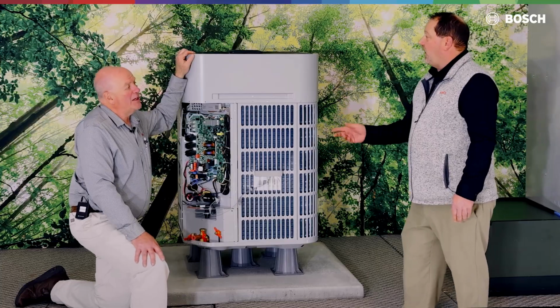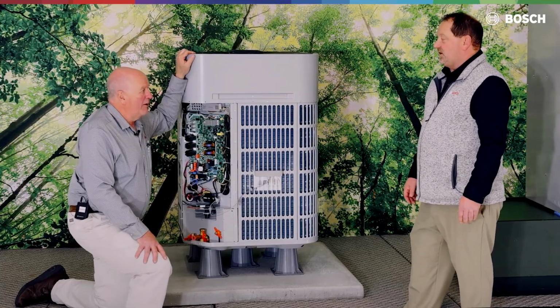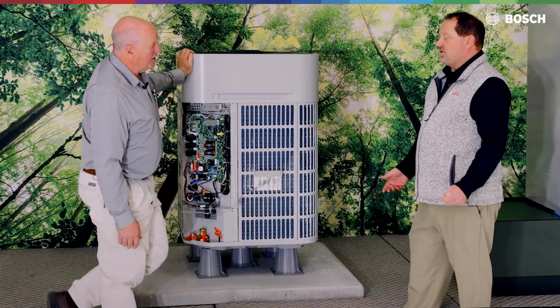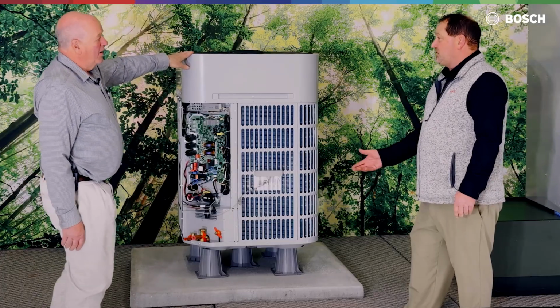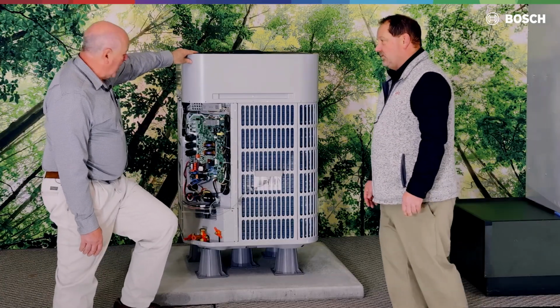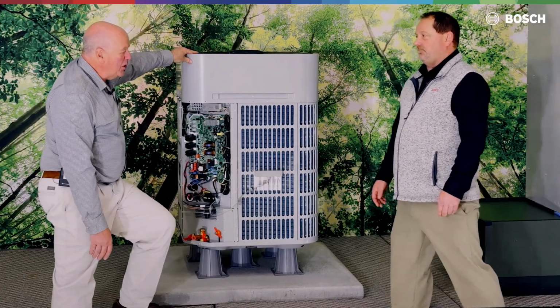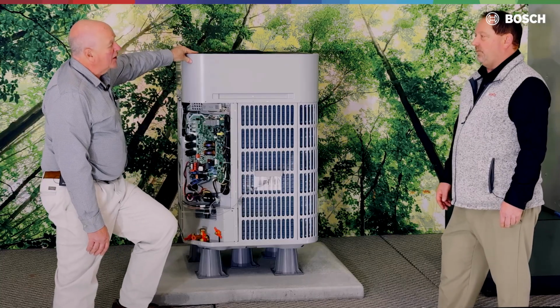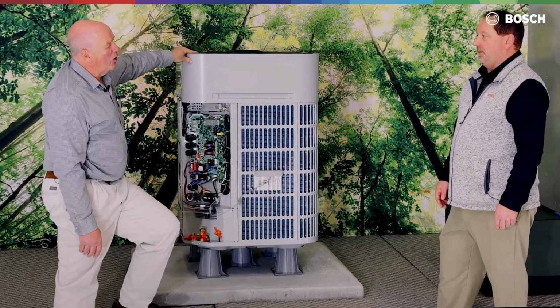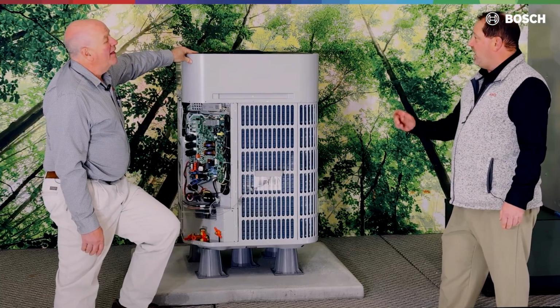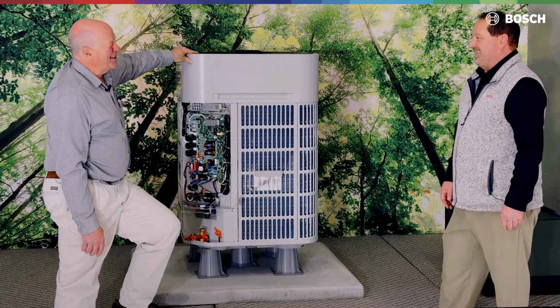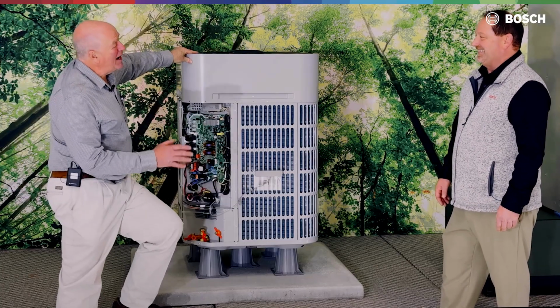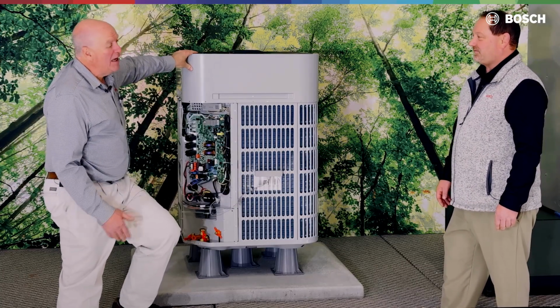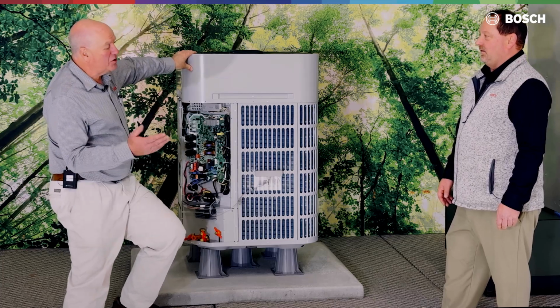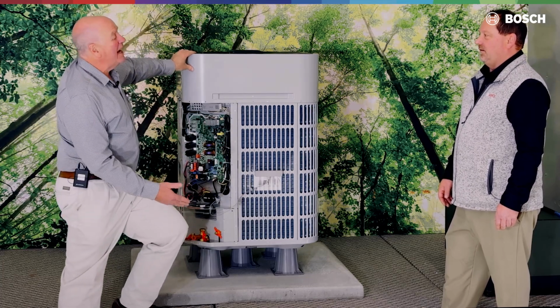On the original 410As, it was 150. On the 454B, it's 250. So now we're up to 250. We're going to be very prominent with that. We're using nitrogen to pressure test. Chris, does nitrogen change pressure at all with temperature? Well, it might a tiny bit. It does not. So it stays the same, and that's the benefit of putting in your pressure at 250. If you have 250 nitrogen, whether it goes to 0 or 80 degrees, it's still 250.